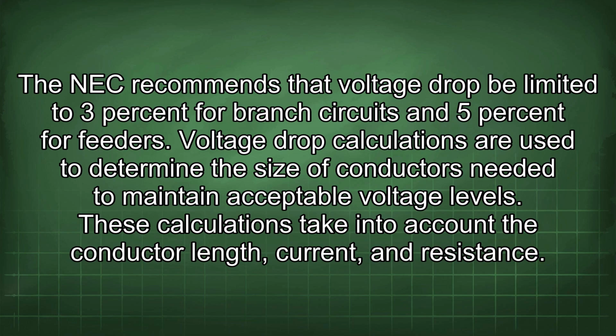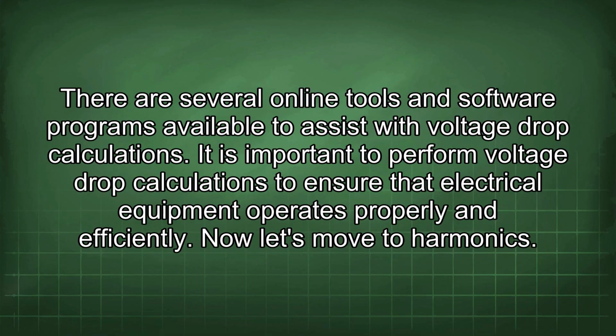Voltage drop calculations are used to determine the size of conductors needed to maintain acceptable voltage levels. These calculations take into account the conductor length, current, and resistance. There are several online tools and software programs available to assist with voltage drop calculations. It is important to perform voltage drop calculations to ensure that electrical equipment operates properly and efficiently.